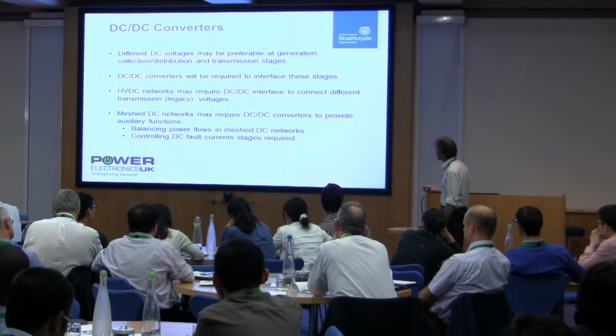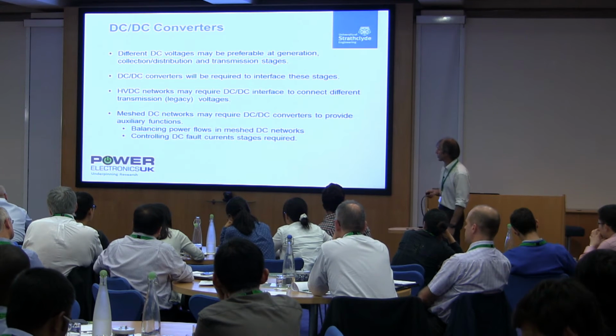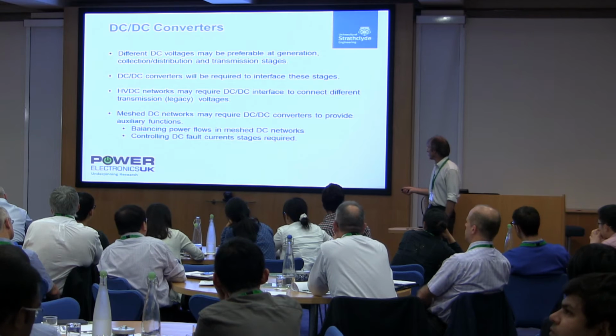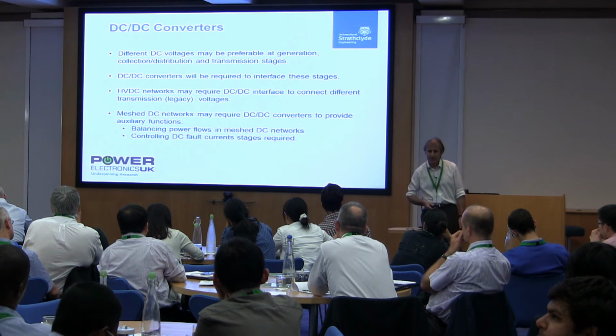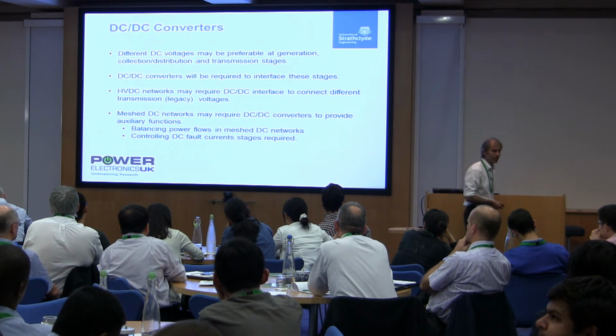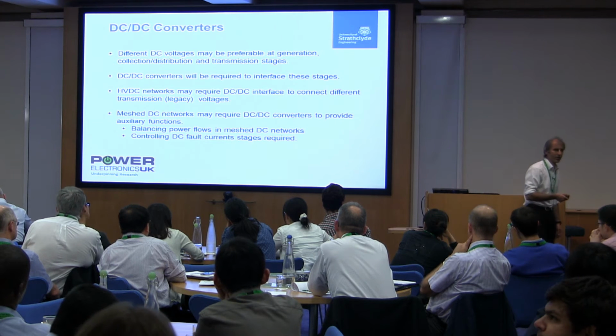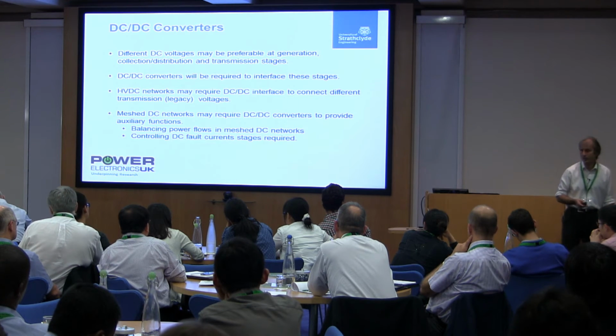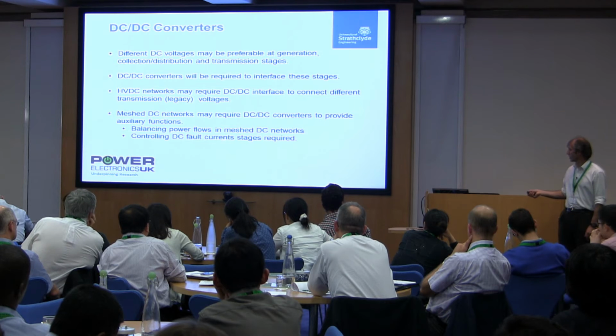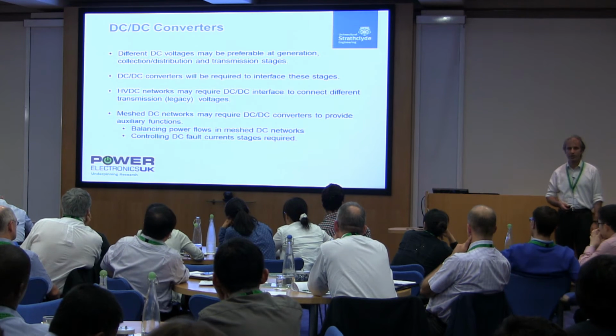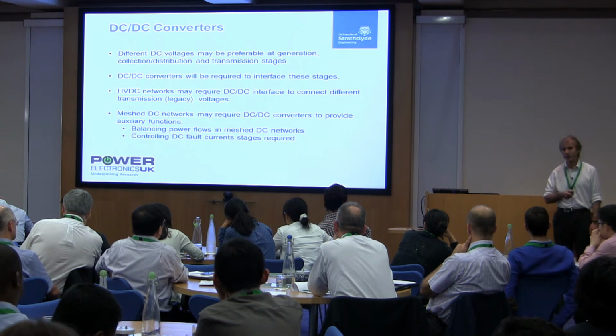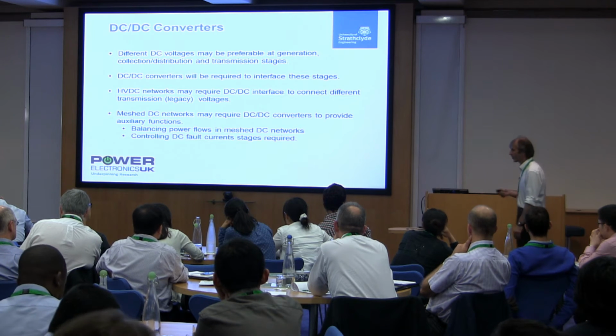There may also be a need for DC to DC converters to provide auxiliary functions. Principal drivers for that would be balancing power flows in mesh systems, allowing you to optimally share the use of the conductors, or controlling DC faults. Once you've got a DC to DC converter in the circuit, it automatically provides that circuit breaker function, though whether it's justified to put one there purely for that purpose is another matter.